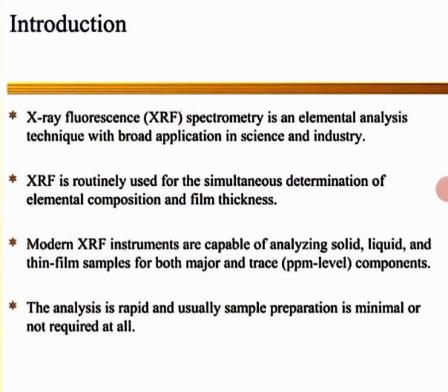Modern XRF instruments are capable of analyzing solid, liquid, and thin film samples for both major and trace ppm level components. The analysis is rapid and usually sample preparation is minimal or not required at all.